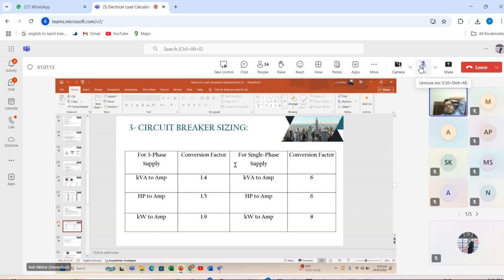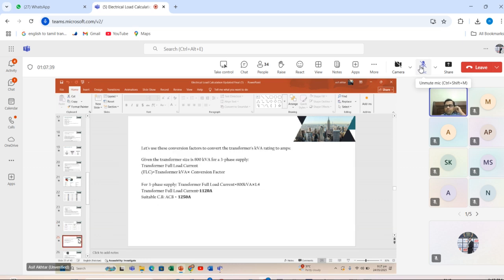Okay. In this calculation, we will use these types of formulas. For three-phase, kVA to ampere the conversion factor is 1.4, HP to ampere 1.5, kilowatt to ampere 1.9. For single-phase, kVA to ampere the conversion factor is 6, HP to ampere 6, kilowatt to ampere 8. For example, let's use the conversion factor to convert the transformer kVA rating to ampere.